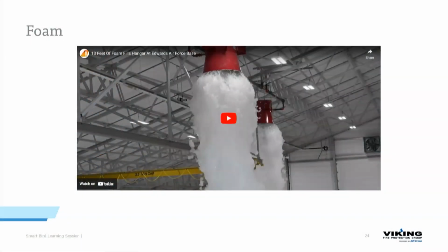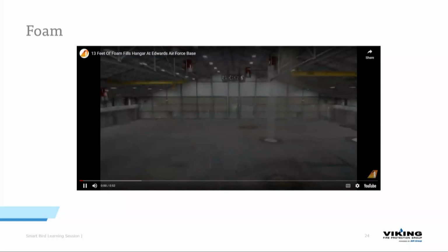So here you go. So these are generators, and there's two components here. There's a fire pump that has water backed up to it, and there's a foam tank. They slam the foam and water together in a proportioner that gives you basically the mix of foam and water that fights the specific type of fire that you're looking for here. So we'll go ahead and watch.